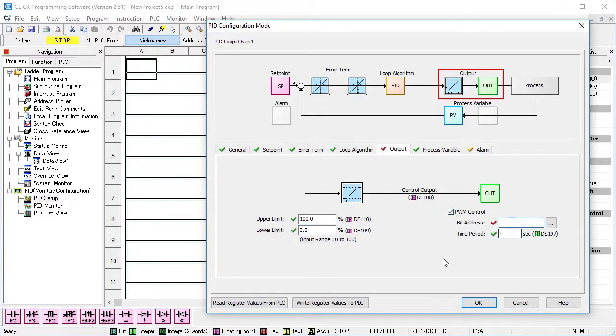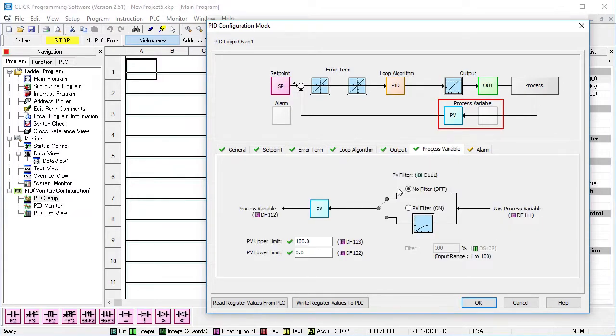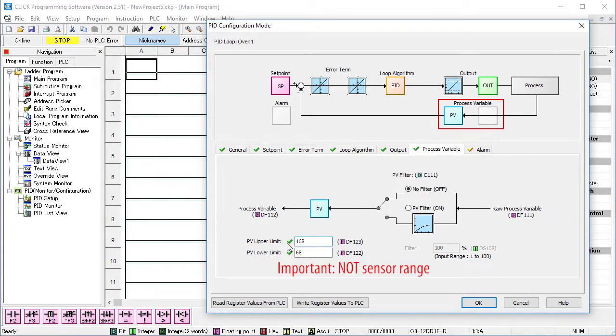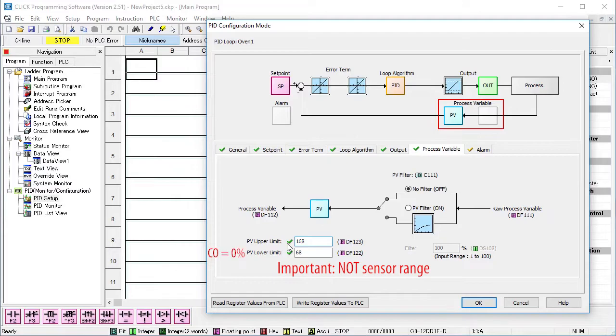In the process variable tab, we tell the PID algorithm what the expected max and min process variable will be. It's important to understand this is not your sensor's range. It's the process variable value you expect to see when the control output is zero and when it's 100%. That provides the scaling that PID needs to make everything work so it's really important you don't miss that one.